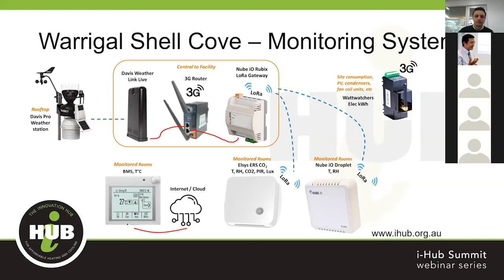That communicates wirelessly to a 3G router, central within the facility. We're using the LoRa WAN network and LoRa RAW networks to communicate to wireless sensors installed into the individual rooms we're interested in monitoring. This one in the center, at the bottom, is the Elsys ERS CO2 sensor, capturing temperature, relative humidity, CO2, occupancy, and lux levels, scattered throughout a number of rooms.